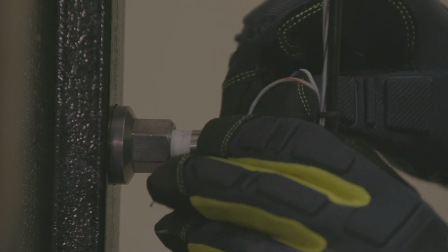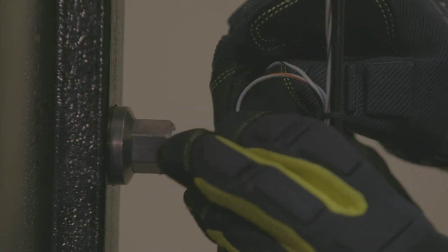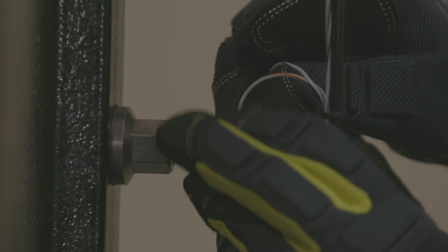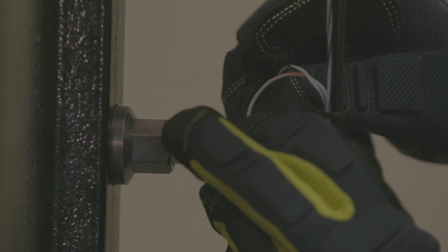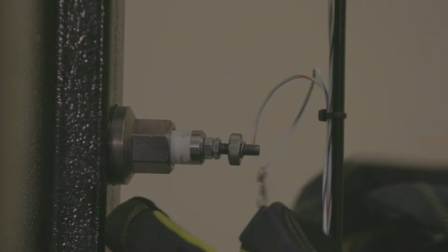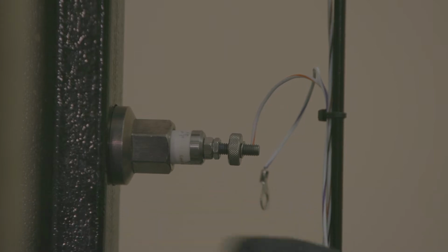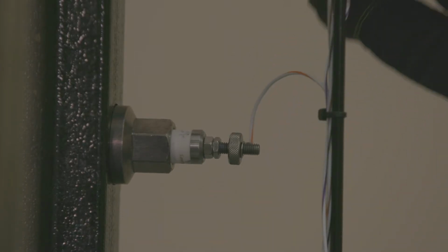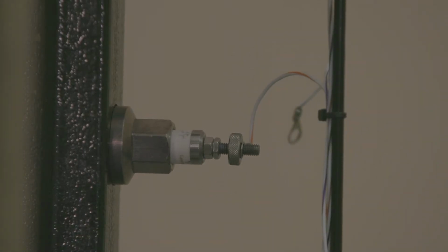All is good. Without the continuity circuit, a dry channel would respond the same way. But since the channel is expected to be dry, there would be no fault. A break in the continuity circuit will cause the channel to show wet, which will induce the fault.